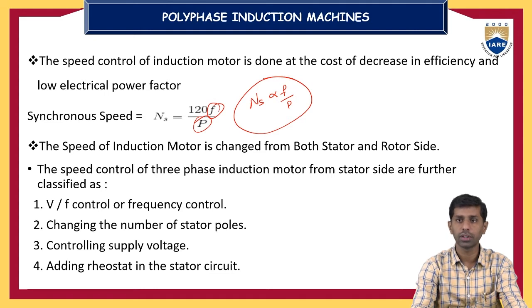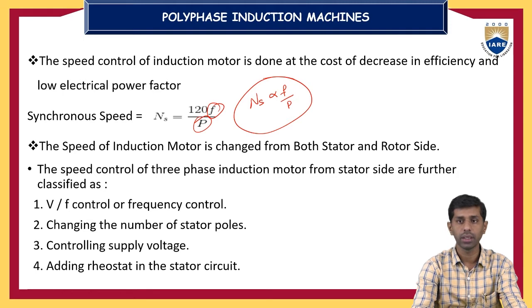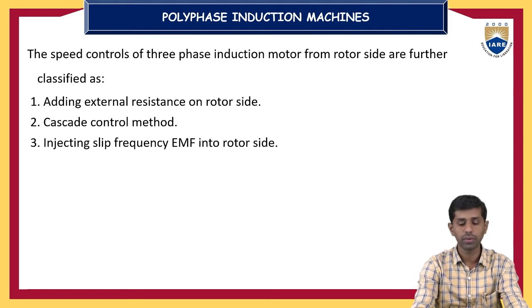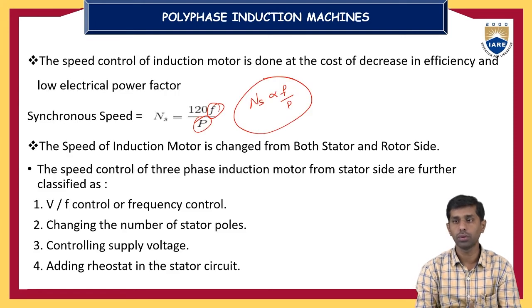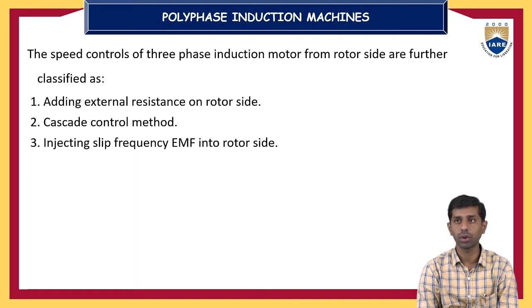Speed control of three-phase induction motor from the stator side is classified into four methods: first, V/f control or frequency control; second, changing the number of stator poles; third, controlling the supply voltage; and fourth, adding a rheostat in the stator circuit. From the rotor side there are three methods: adding external resistance on the rotor side, cascade control method, and injecting slip frequency EMF into the rotor side.